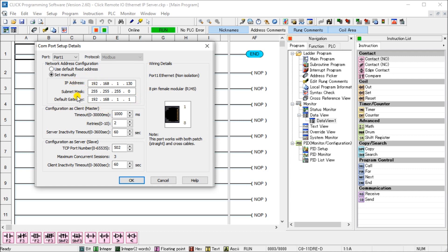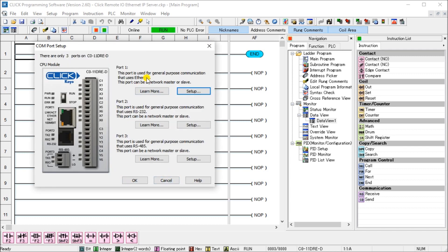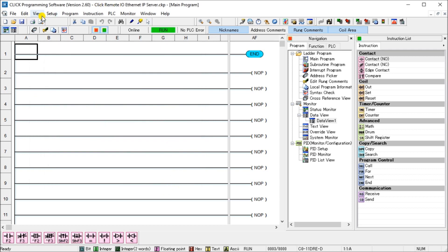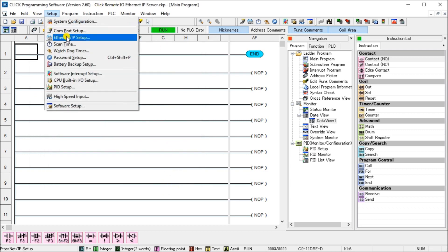Under Setup you'll see that we have manually set a static IP address for this Click PLC. We need to use a static address so that the scanner can actually see the adapter we're programming here. The address is 192.168.1.130 with a subnet mask of 255.255.255.0. The default gateway doesn't matter much in our case. That is our port setup.